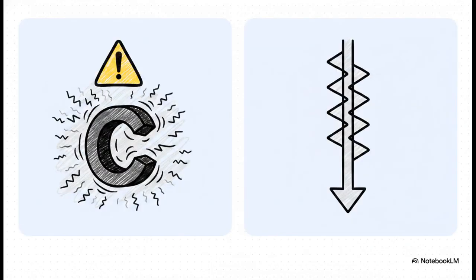When you contrast the two technologies side by side, the fundamental difference really just comes down to the core. The traditional VT relies on a magnetic core, which means it carries the inherent physical risks of saturation and ferroresonance. But the resistive divider has absolutely no magnetic core. Because there's literally no iron core to saturate or resonate, the risk of ferroresonance is physically zero. It's a purely linear drop through a resistor stack. No core, no phantom faults.